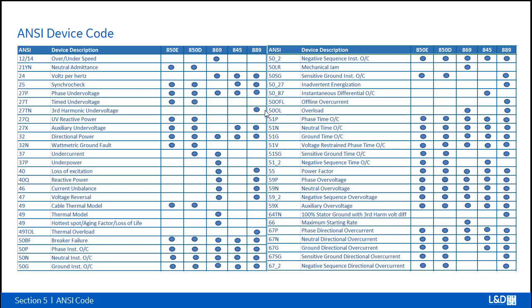And for the specific elements, we see that 869 has the most specific elements. For example, over/under speed, underpower. Undercurrent used to be only for 869, but from the new version 2 of 850D, we also have undercurrent. Then we have this thermal model, which is a specific motor thermal model. This thermal model is different from the feeder relay 850 cable thermal model.